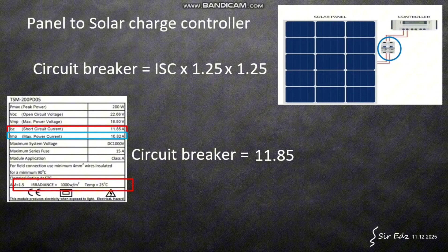So we just get the ISC which is 11.85. Actually, this is just for one solar panel, that's why it's 11.85. But if you have several solar panels or several strings or PV modules connected in parallel, you need to get the total ISC. Here, we only use one panel.